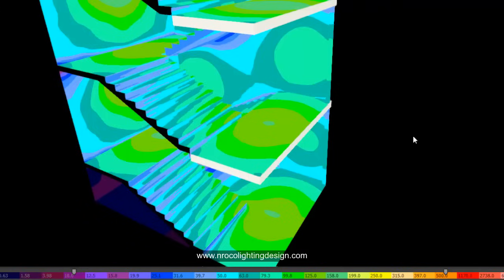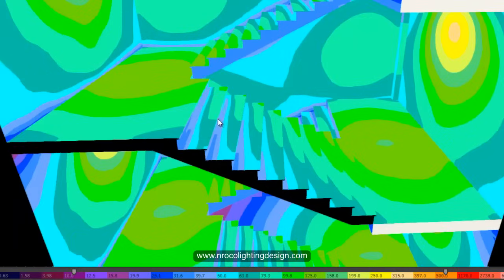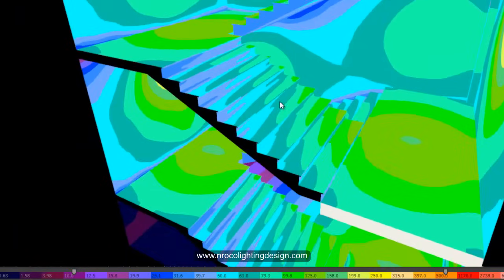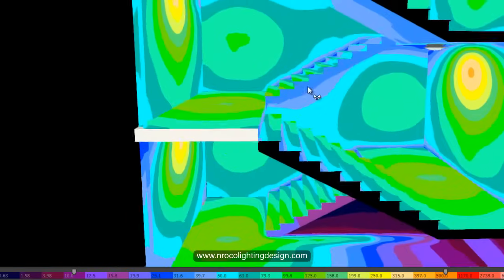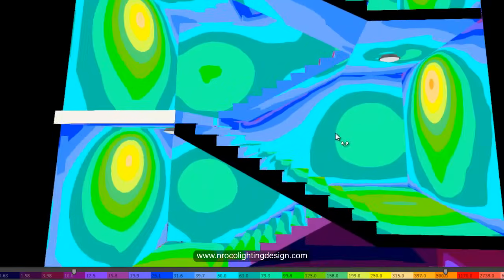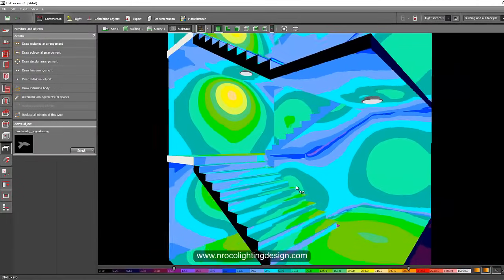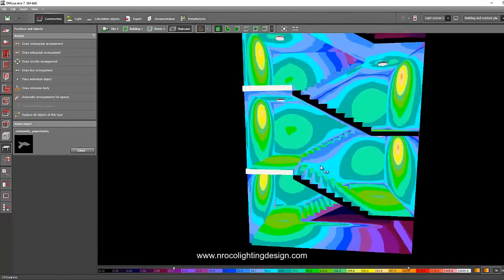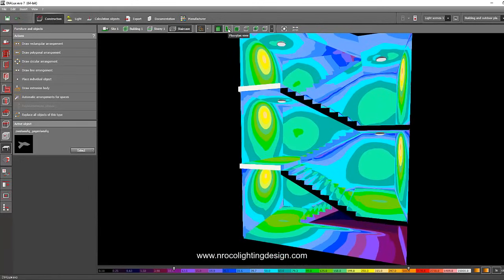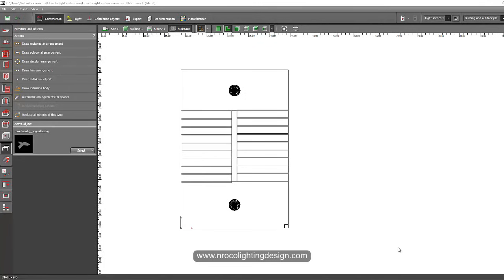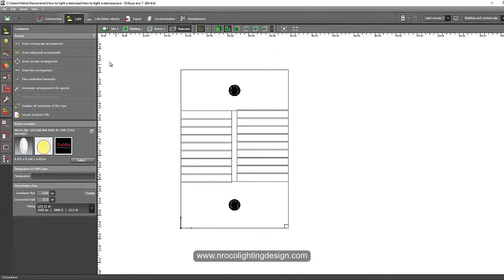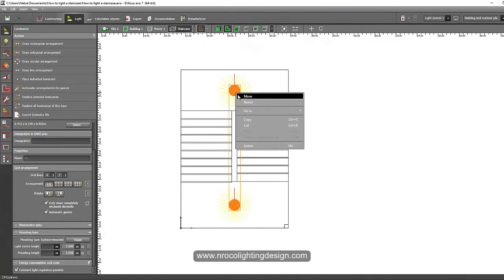The yellow-green indicates about 125 lux and the cyan ranges from 79 to 50 lux. The staircase is too dark — we need at least yellow-green on the treads. This layout with one luminaire is not enough, so let's add another fitting and see how it looks. Discard the result, go back to the plan view, and add one more fitting to the side.